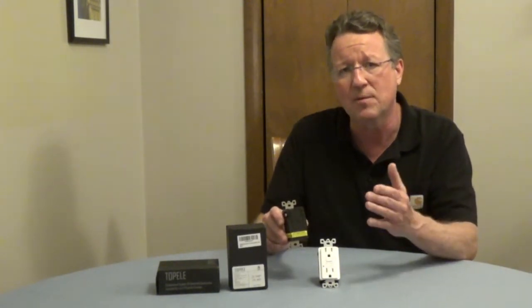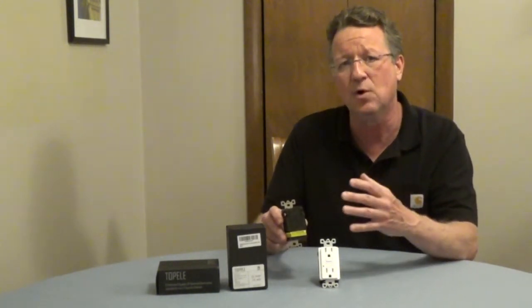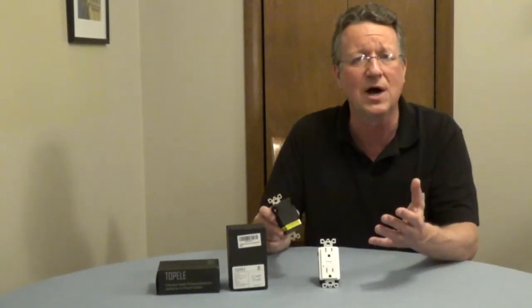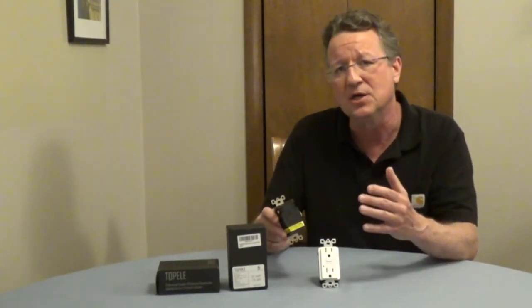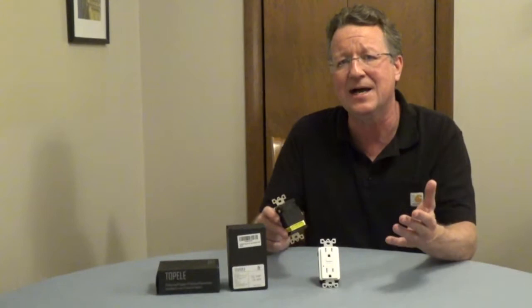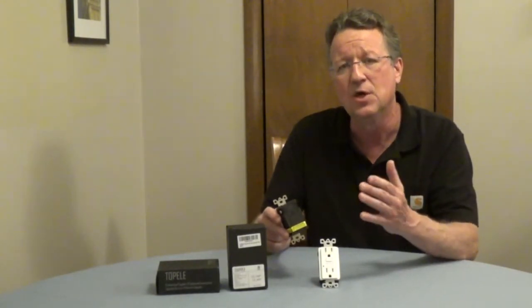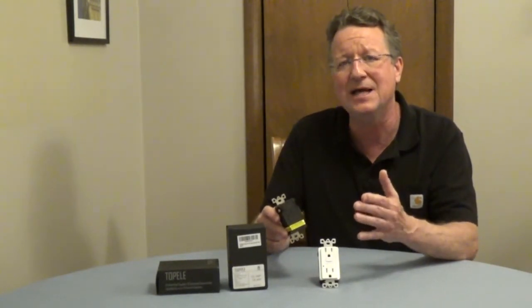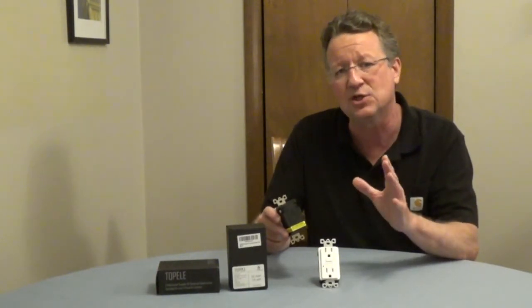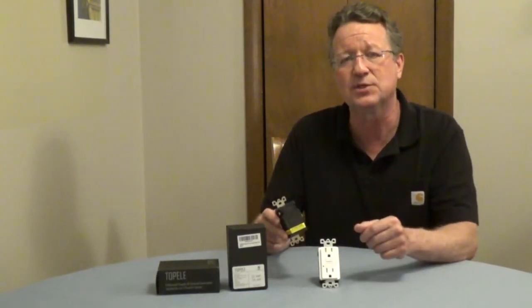So you're going to turn off the power, make sure it's off, remove the old outlet. You're going to separate the wires so nothing's touching. You're going to turn your power back on, and you're going to test the two black wires. When you find the black wire that's hot, you're going to mark that wire, and that's your hot cable coming from the service panel.